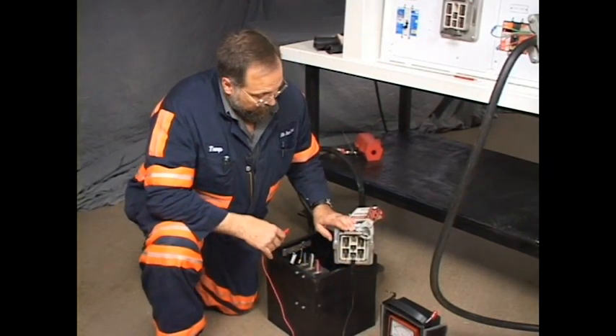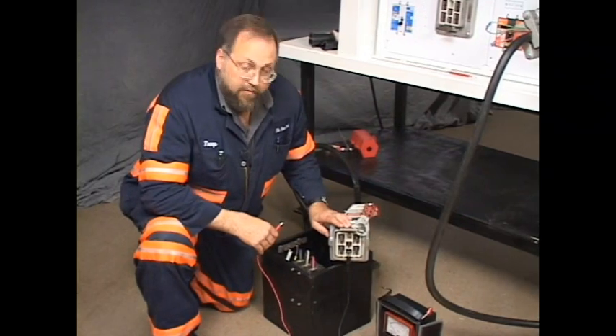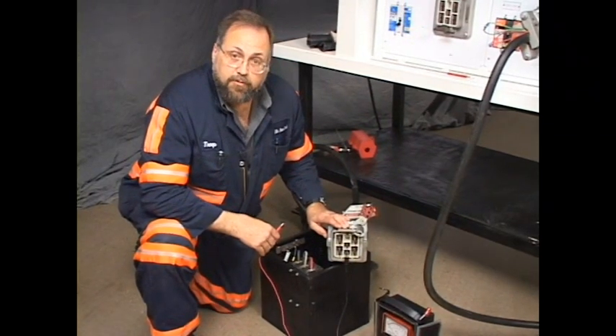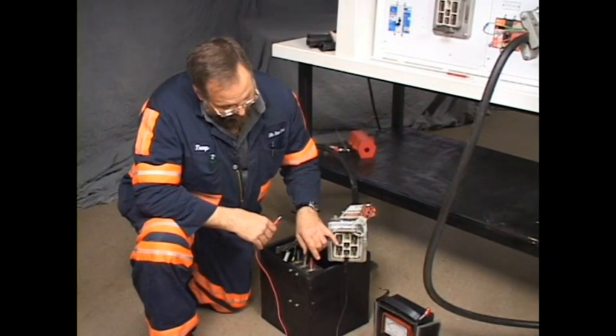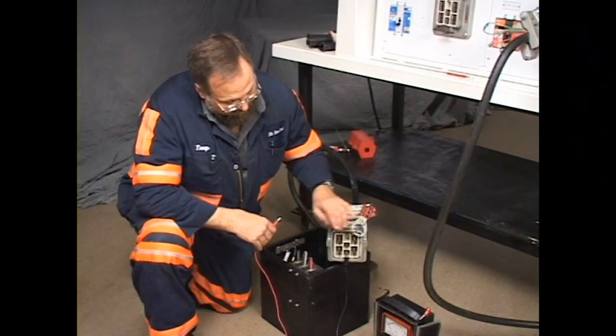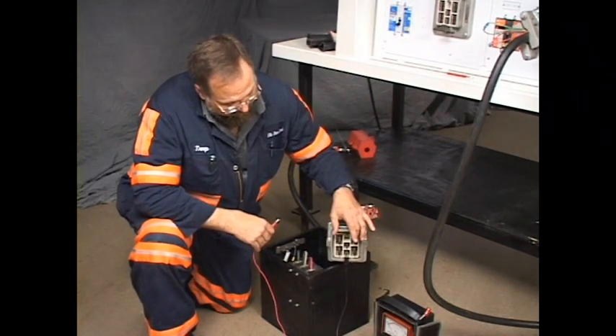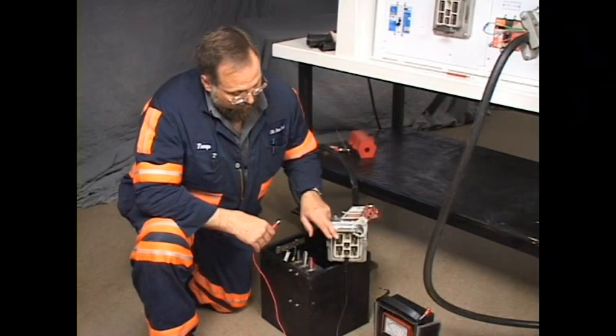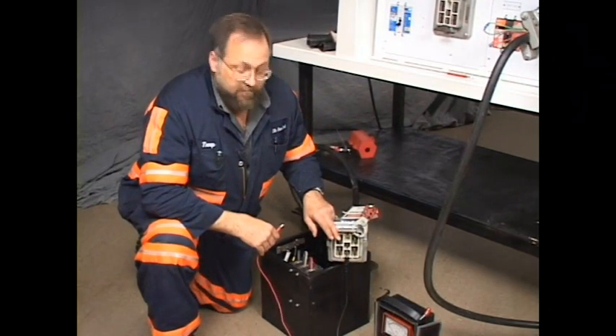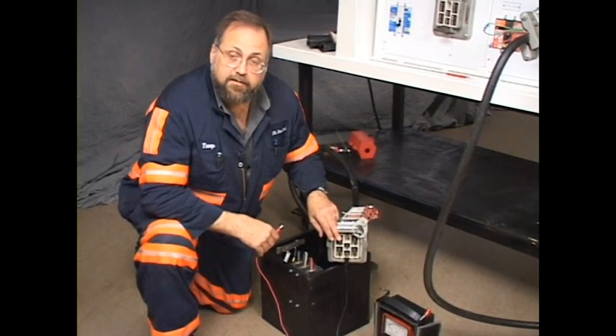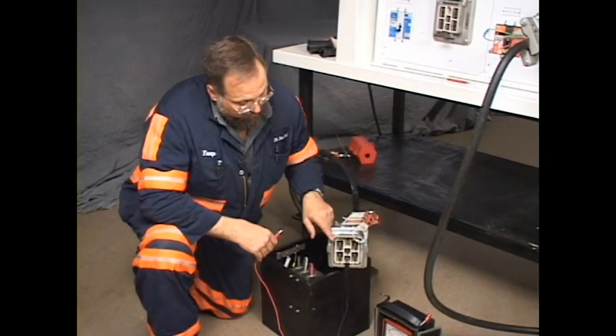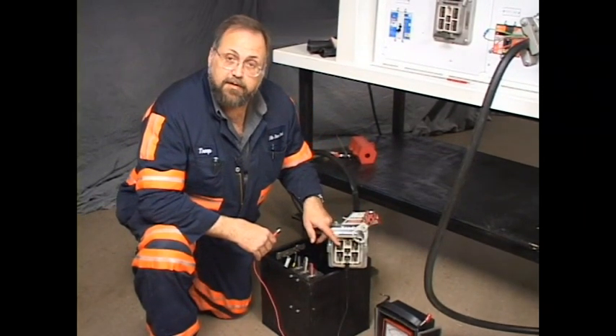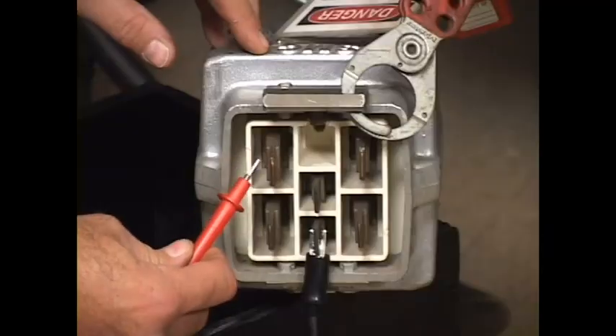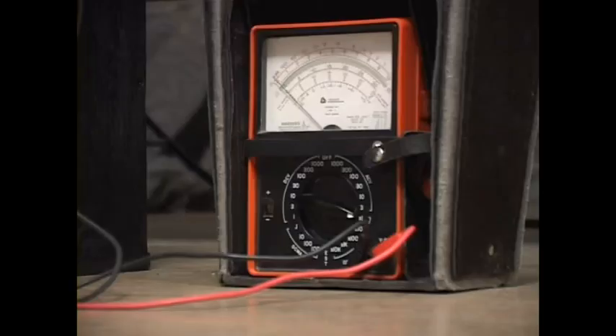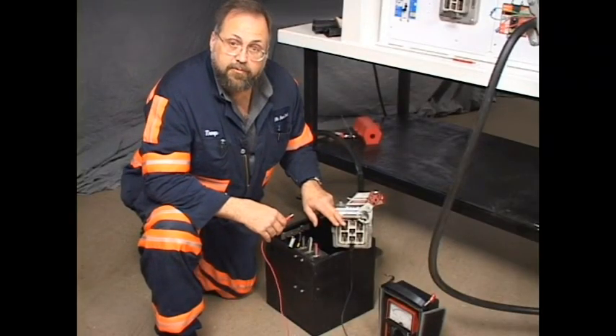According to your studies as well, the ground blade is the last one broken. These blades are cut at an angle with a long edge and a short edge on top here. As this thing is levered out, the long edge will stay in contact after this one is broken. The ground is supposed to be broken last. That's my ground blade. And we have an open circuit. This should read continuity, but it does not.